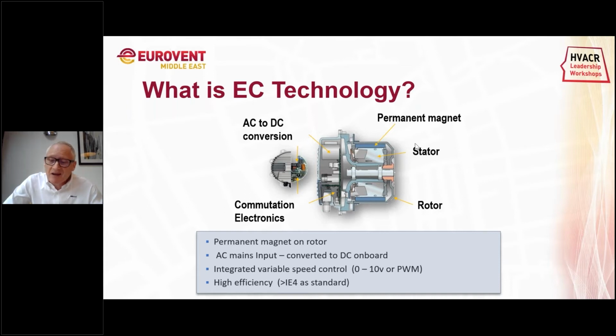As we said earlier, there's no need to worry about DC supplies for sensors. So if you wanted to put a sensor straight onto the motor, like a pressure sensor or a temperature sensor, you can simply connect even a potentiometer to the fan. There's no triacs, no frequency inverters, no whining noises at all. On an EC motor, under speed control it's virtually silent.